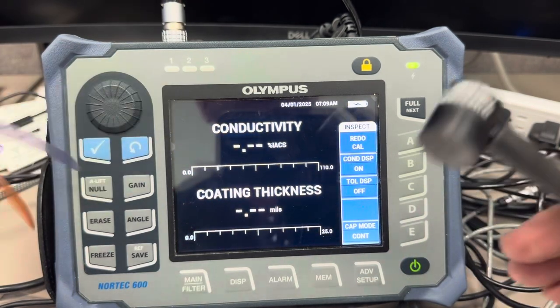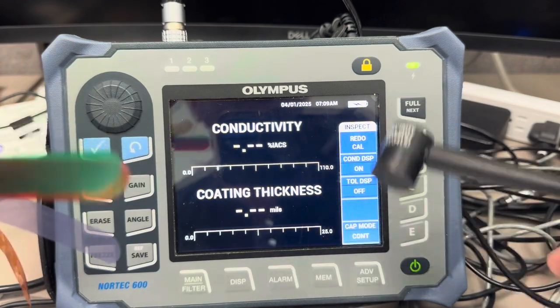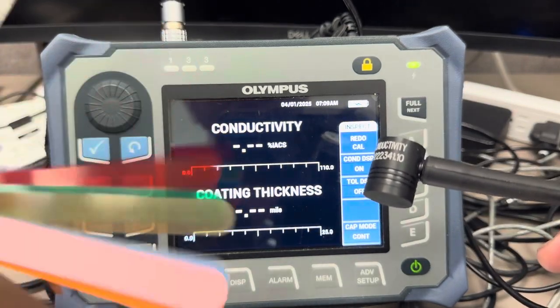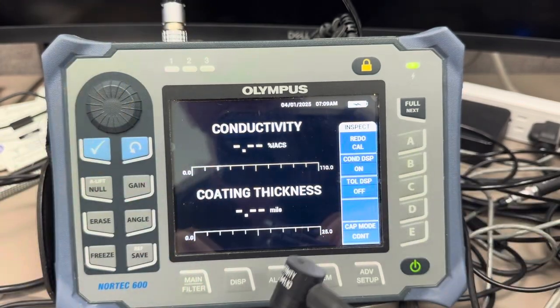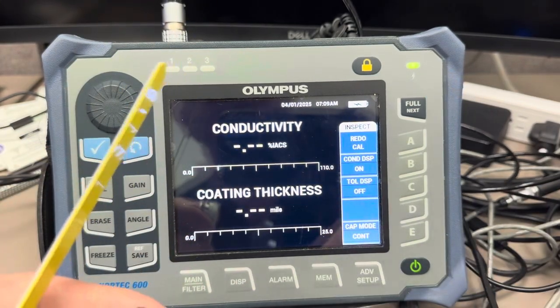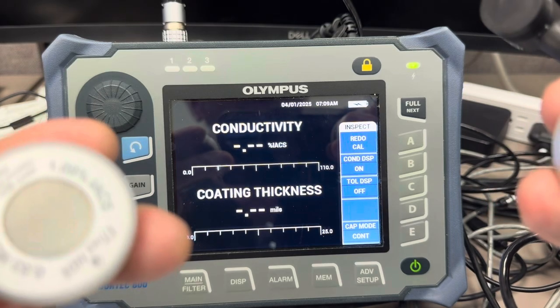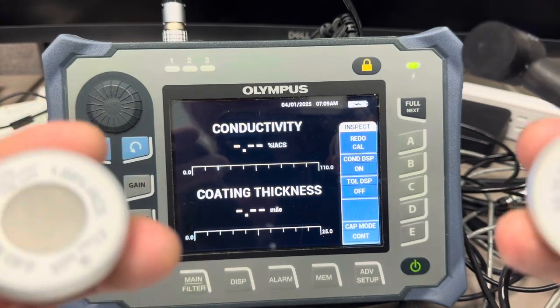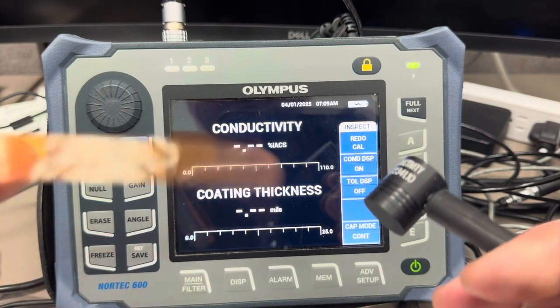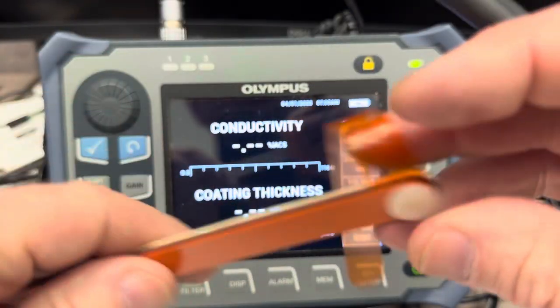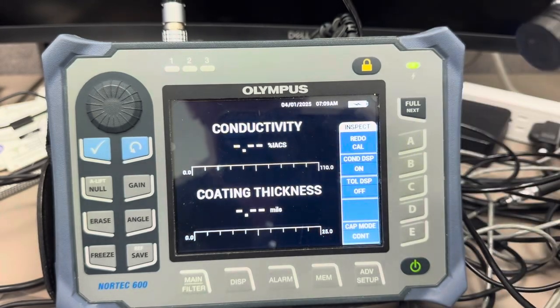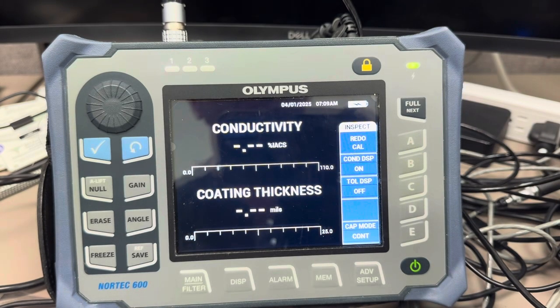So now you can see that it's very easy to set up the Nortec 600 to measure conductivity and liftoff, as long as you have several known samples that you can use to calibrate. And if you want to calibrate for a different range, just find different samples that have the range that you're most interested in. And of course, you always should have calibrated shims like this that are of a known value, so you can have a more accurate setup. All right, I hope you enjoyed the video.